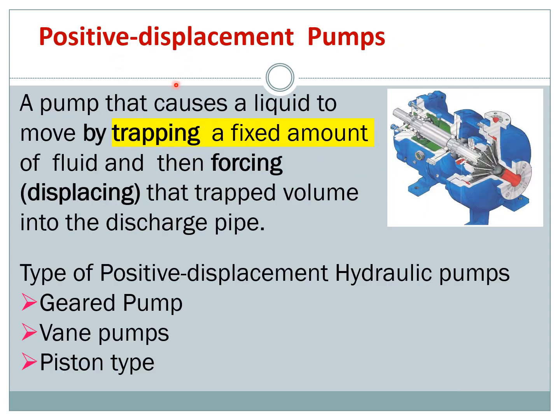The second type is the positive displacement pump. This is a pump that causes the liquid to move by trapping a fixed amount of fluid and then forcing or displacing that trapped volume into the discharge port. It will first trap a fixed amount then pump it to a particular place. It is not like the non-positive displacement type where it simply takes the input and channels it to another place.